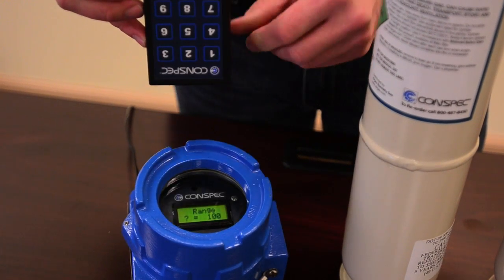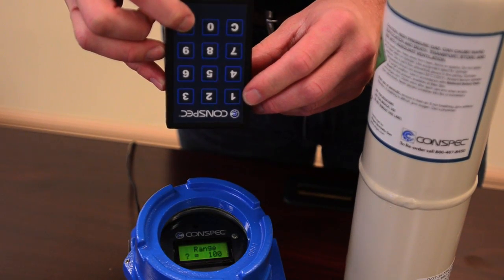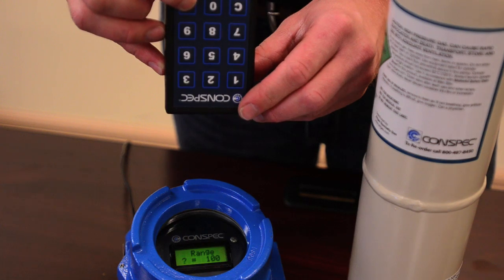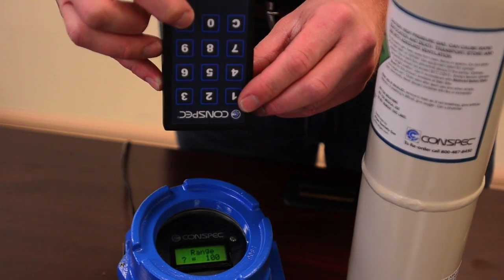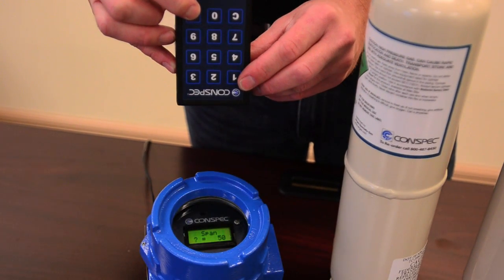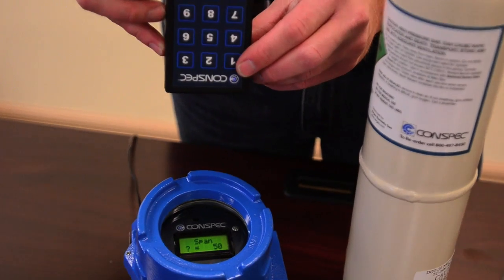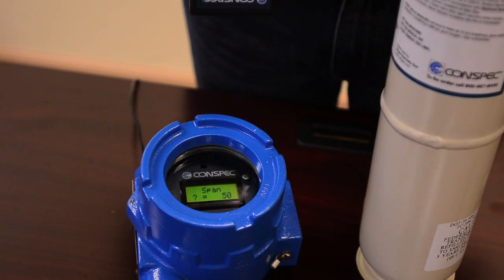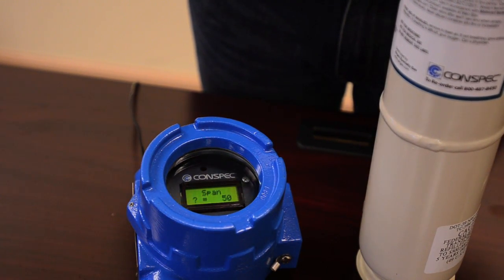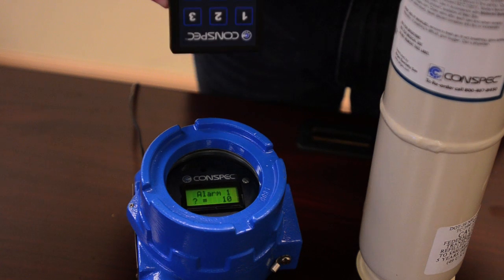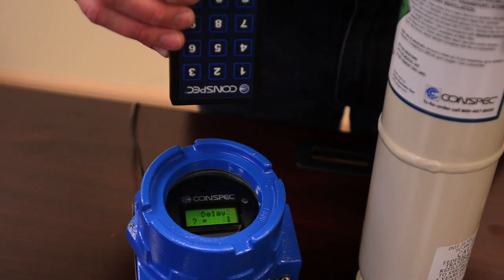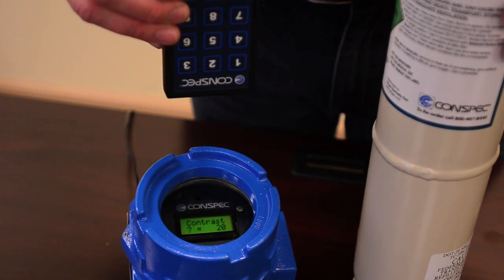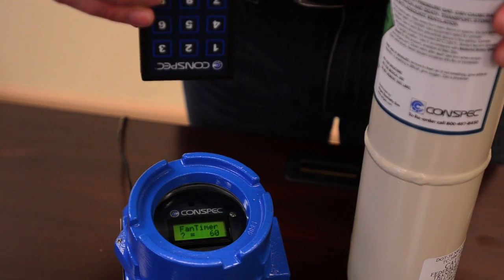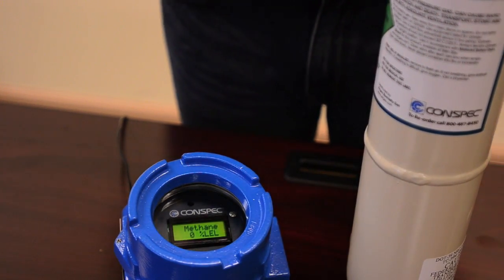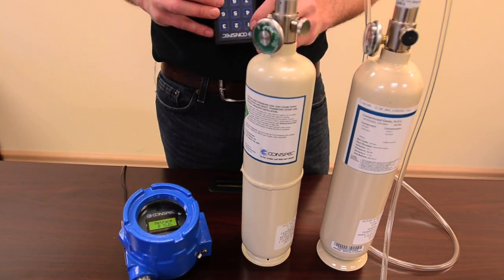Then the next screen displays range 100. As I said, this is a 100% LEL. That's what the 100 corresponds with. Press the enter key. Span value equals 50, which is correct in that we're using half of the span to calibrate. And then the rest of the screens, again, are not relevant, so we can advance past those and get the monitor back into monitoring mode. So now we're ready for calibration.